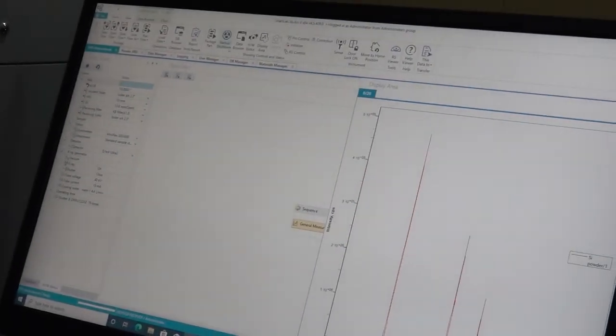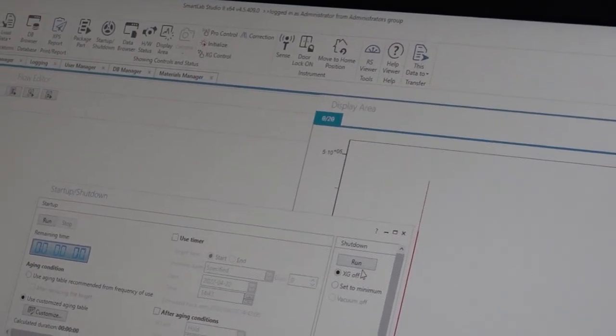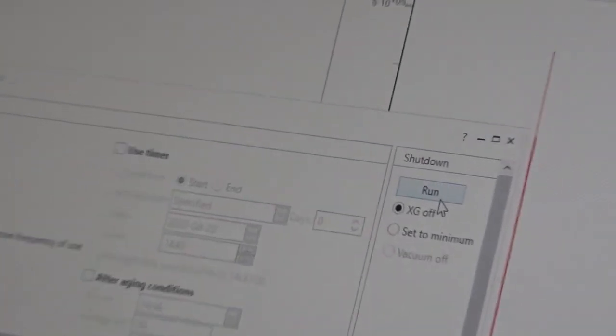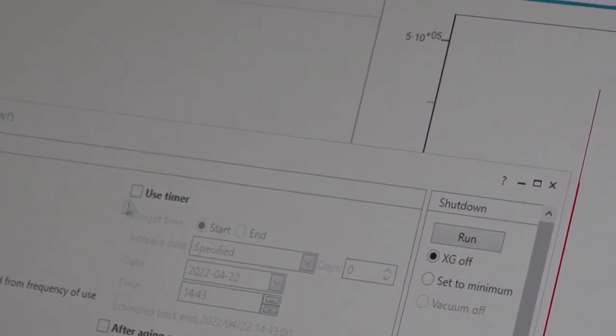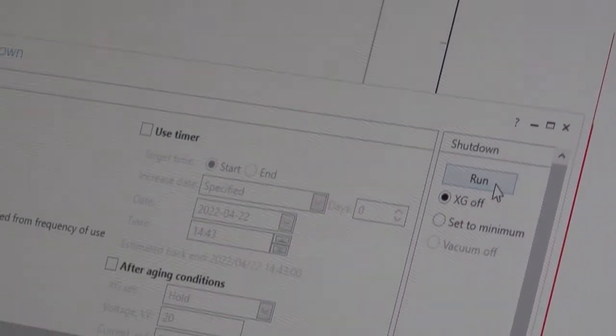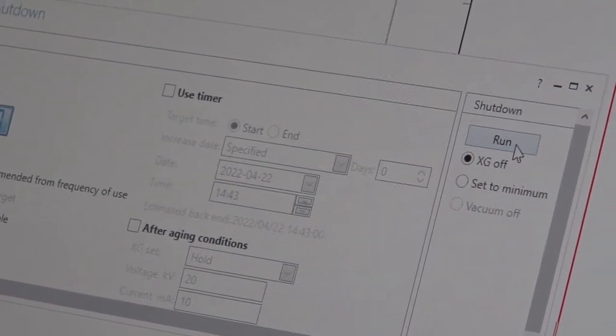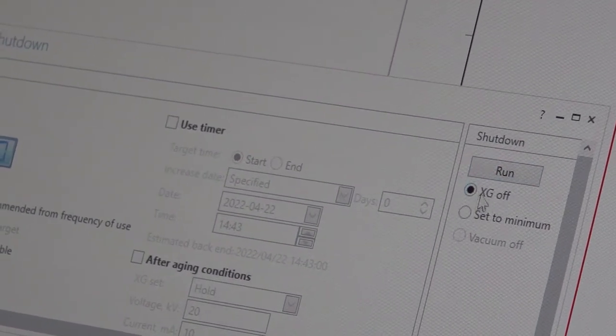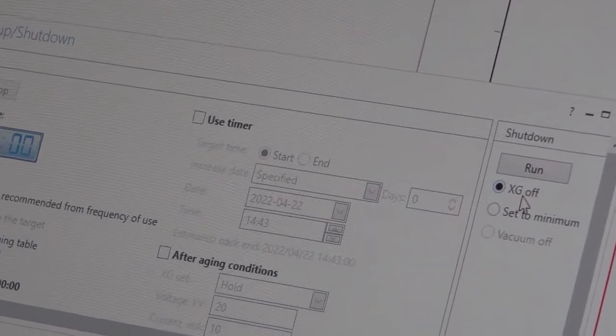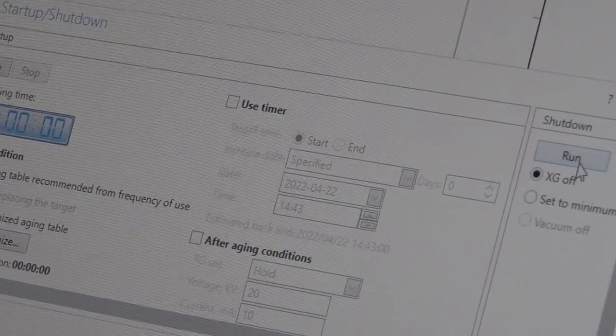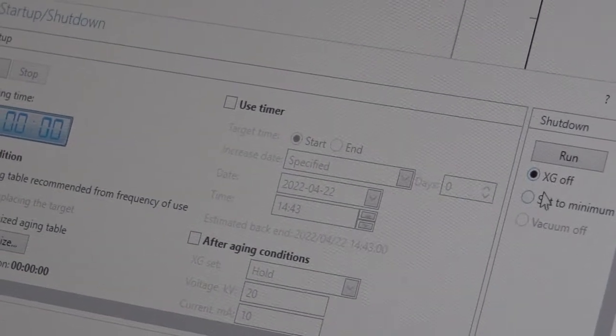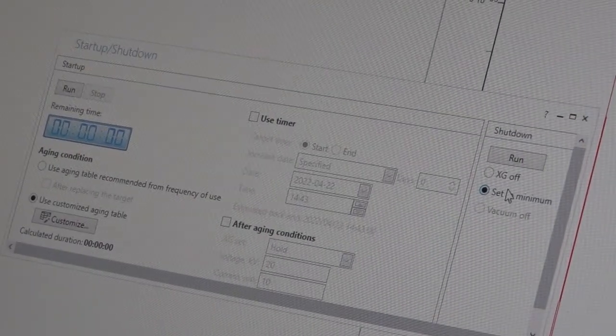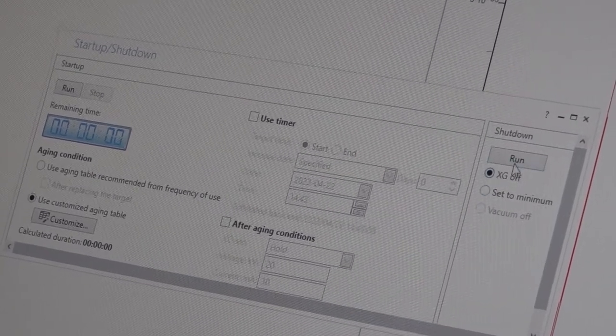If you have any doubts, you can ask. See, the shutdown process also. This startup is there, no? Again you go there. Here, shutdown run is there. While shutting down, not like this slowly, it is not required. Just run the shutdown. Slowly it will come down and it will shut off the X-ray. You can see here now. See, again two options are there. XG off means you should switch off the XG control. When you run this, the X-ray will completely switch off. Suppose set to minimum, it will come to 20 kV and 2 milliamps.